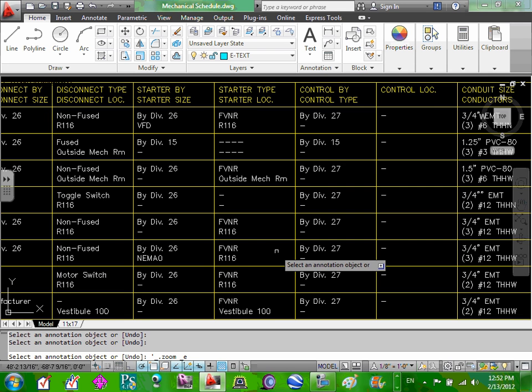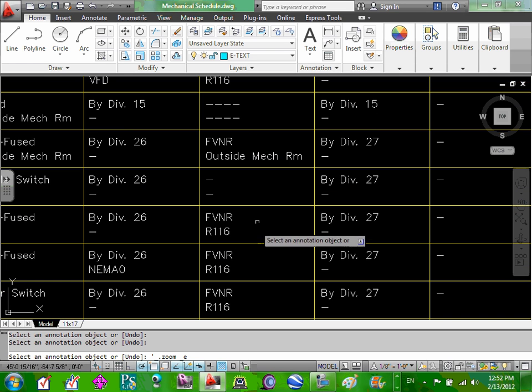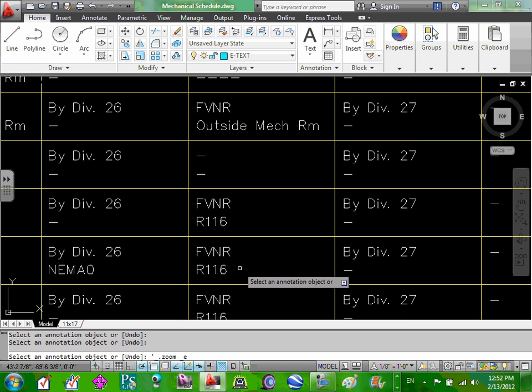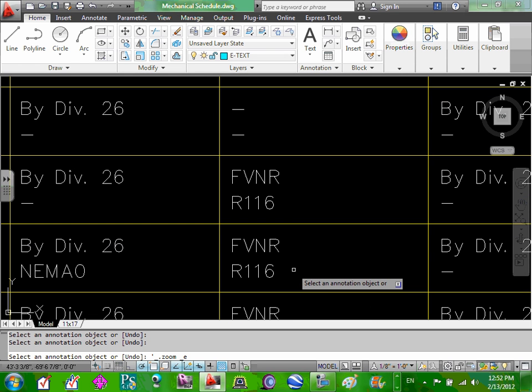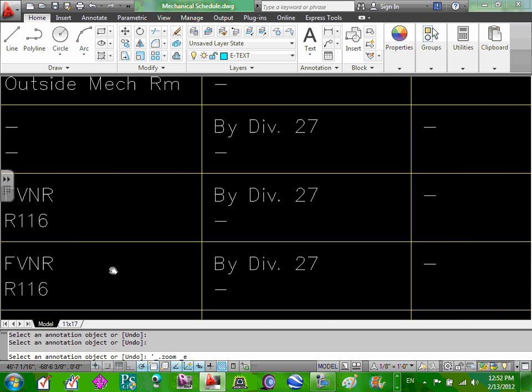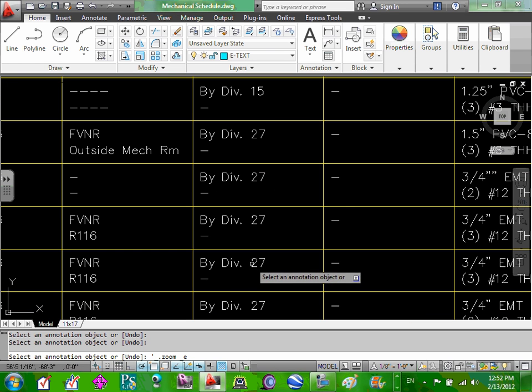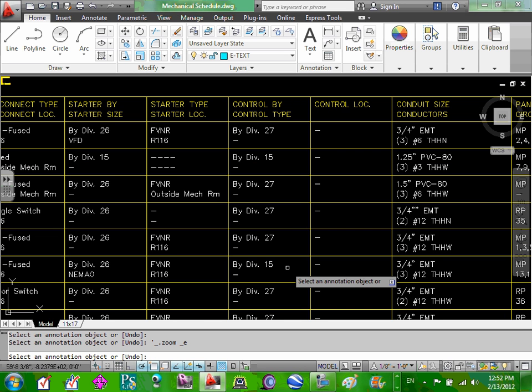Okay? Any questions, guys, about the NEMA, these two, the NEMA size and the NEMA type? Does it make sense? It's always full voltage, non-reversible, unless they tell you they need to reverse the motor. Okay, so let's go back here. Division, I'm going to say division 15 here until we figure it out. Division 15 is providing the control, always the mechanical equipment control, guys, division 15 for the most part.